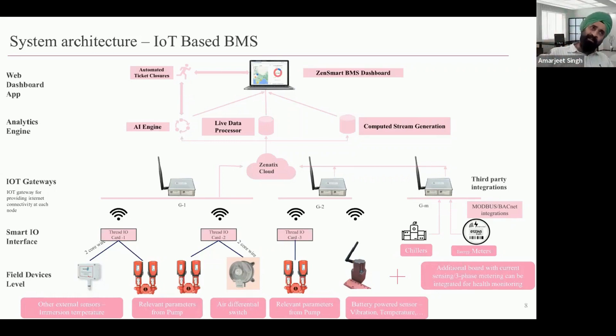Rather than simply giving a higher-level diagnosis like low temperature or high CO2, you also get real-time visibility of data and tickets. It's a two-way communication — you can push back controls as well. And those controls are not only managed in the cloud. At every layer of this IoT architecture the systems are smarter: the local PID logic runs on the IO card itself at the lowest layer, which means that even if the IO card gets disconnected from the gateway, it will keep doing its own operation. There is also edge intelligence at the gateway level, so even if the gateway gets disconnected from the cloud, it keeps operating intelligently.